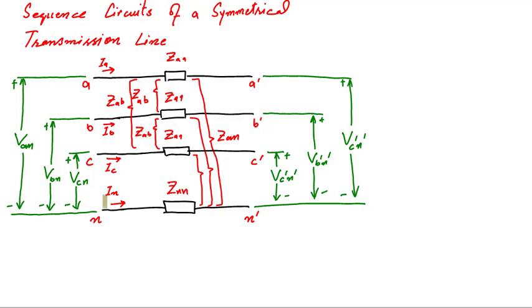In the same way, here we have a neutral conductor return path. In a three-phase transmission line, as there is no overhead conductor used for the return path, no neutral conductor, in that condition ground will act as a return path. So neutral is always involved. Whenever unbalancing happens, current will pass through that neutral path. If that neutral path does not exist, zero sequence current will not exist.